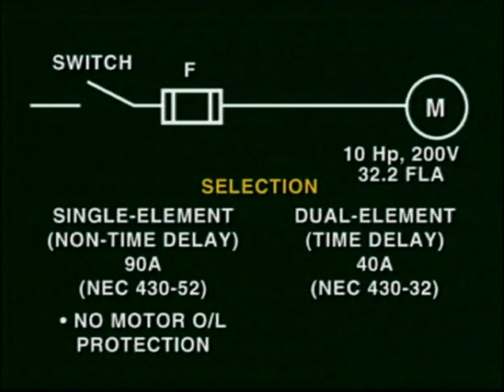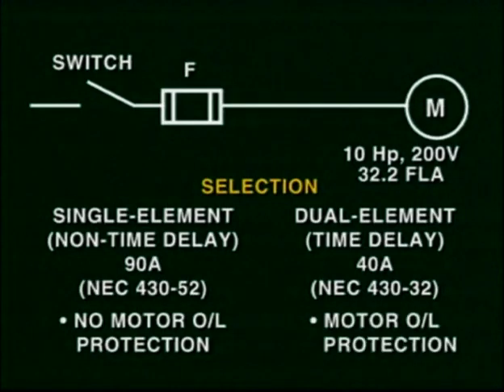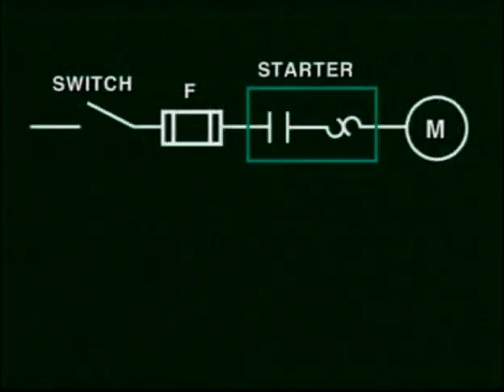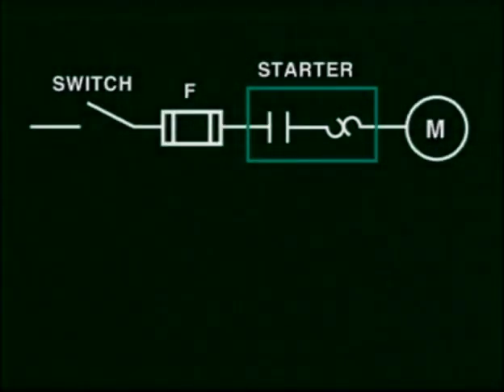This fuse will protect the circuit against short circuits, allow the motor to start when it pulls the starting inrush current, and protect it from overload conditions. In fact, if the motor overload relays are used in the motor control circuit, the dual-element fuses will serve as running motor backup protection in case the overload relays are the wrong size or fail to operate.